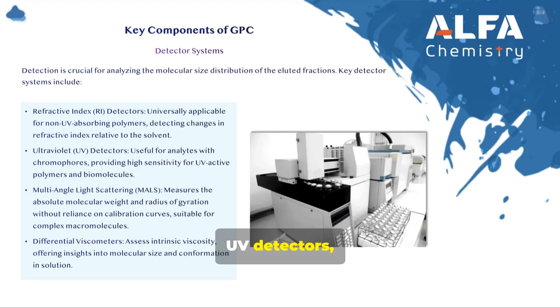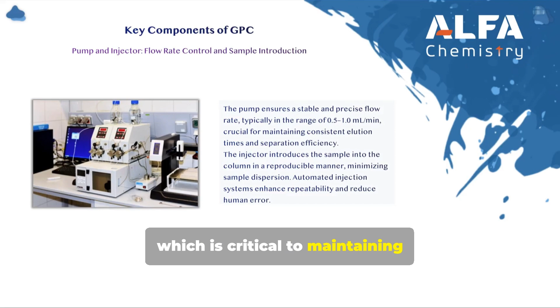And don't forget the pump, the heart of the system, pushing the mobile phase and sample through the column. Pumps ensure stable and precise flow rates, typically in the 0.5 to 1.0 mL/min range, which is critical to maintaining consistent elution times and separation efficiencies.